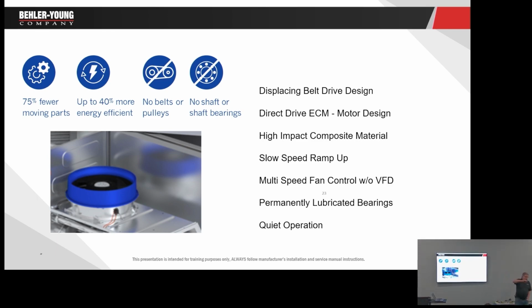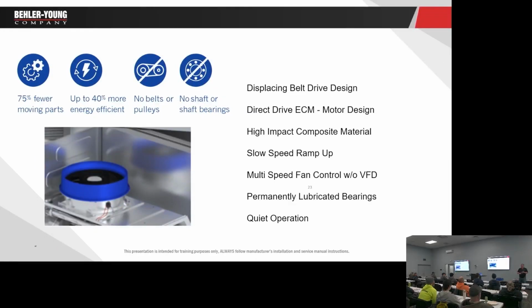Now, if you guys have worked with these, you've had failures, you're like, that motor sucks. Well, generally, 95% of the failures we get with these, like any other ECM motor, are power related. It's a challenge for us. I know, I've been out there. Well, my other unit ran for 30 years. Changed filters, right? And this thing's eating blower motors. When we start digging into the power, they've got power problems in the building. Well, the old unit with the contactor didn't care. This one does. So we'll get into some of the things we can do with power problems later on.